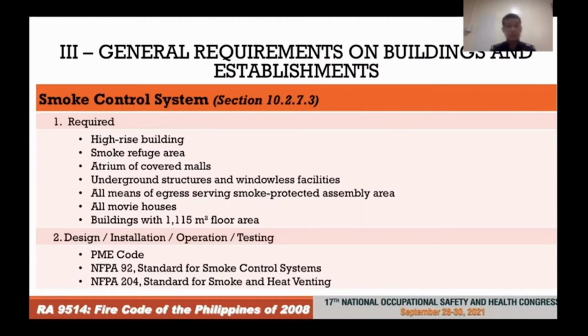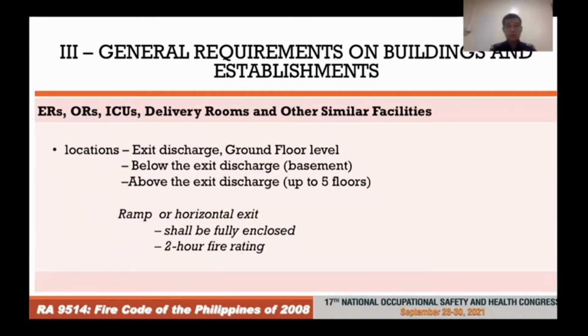Also, I'd like to emphasize for healthcare occupancies or hospitals, we now allow that the emergency rooms, operating rooms, intensive care units, delivery rooms, and other similar facilities may now be located up to the 5th floor. Originally, in the old IRR, we limited the location of these facilities to the ground floor. However, because of several requests and appeals from the stakeholders, we now allow it up to the 5th floor. However, if you're going to locate it on the 2nd floor, 3rd floor, 4th floor, or 5th floor, you have to provide a ramp for use for emergency purposes.